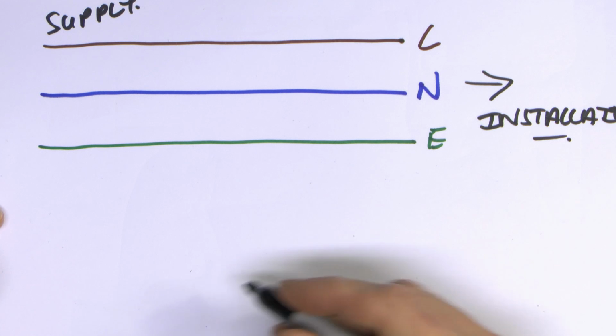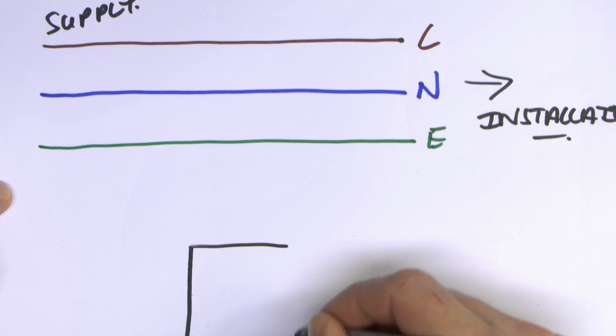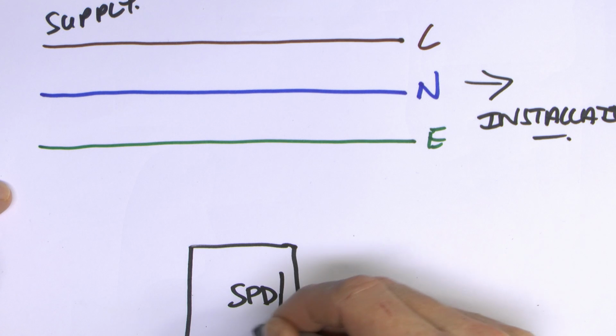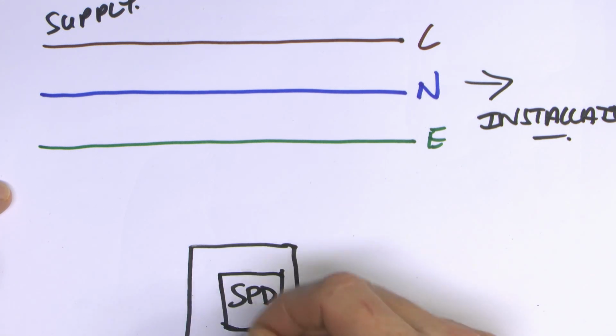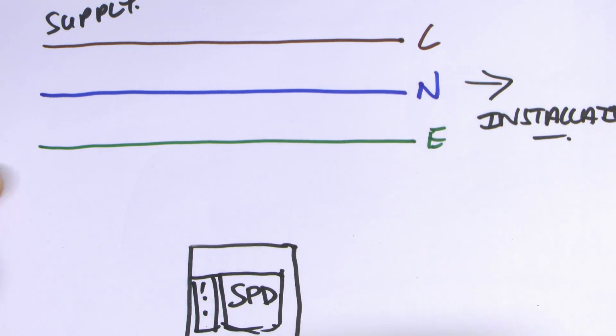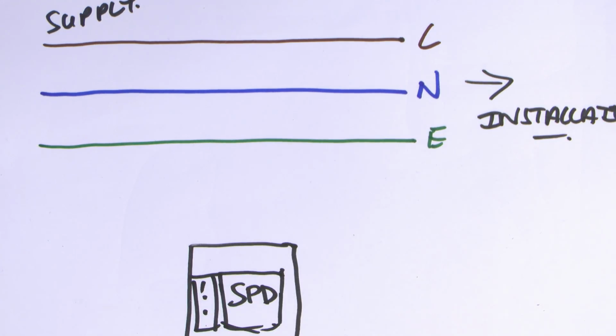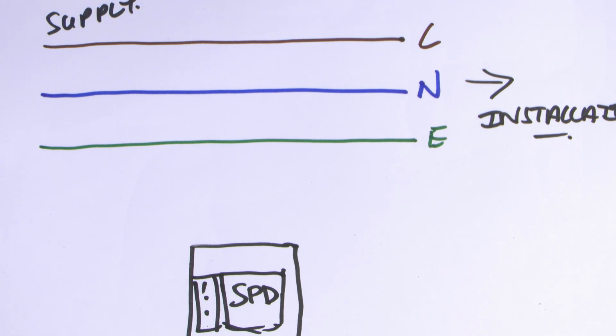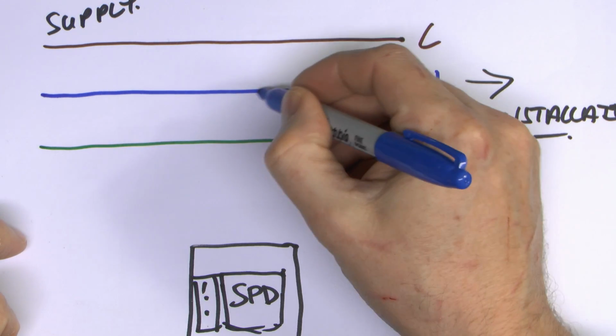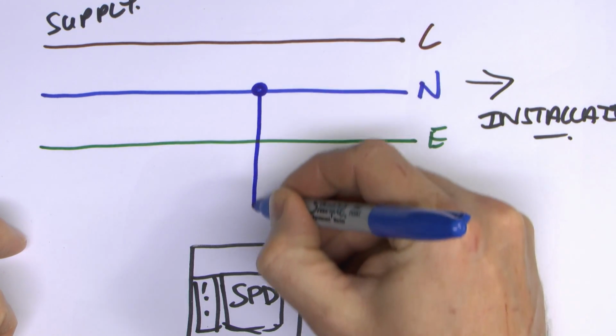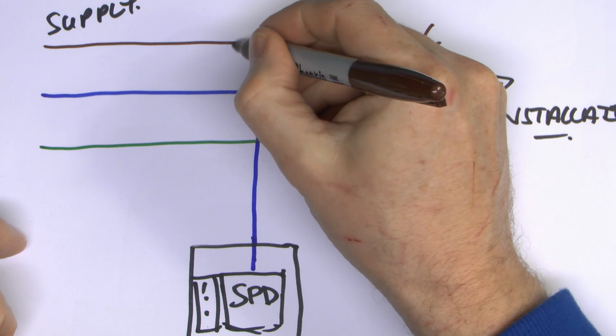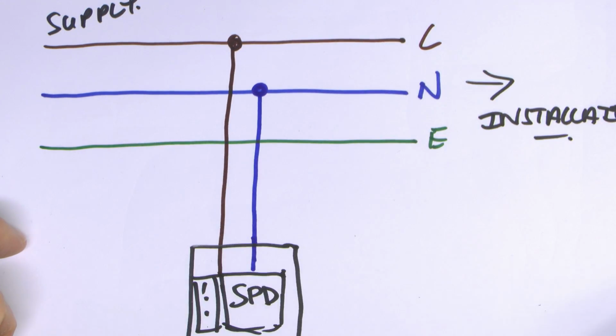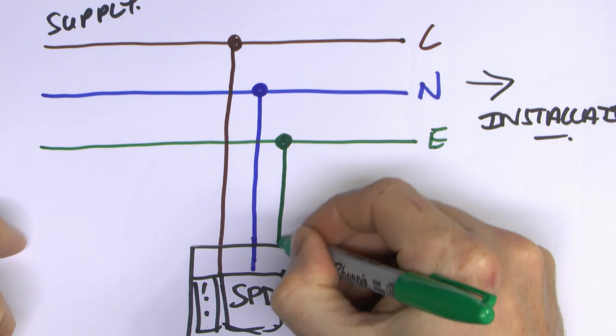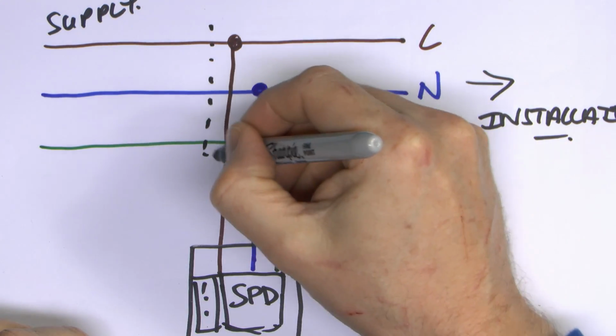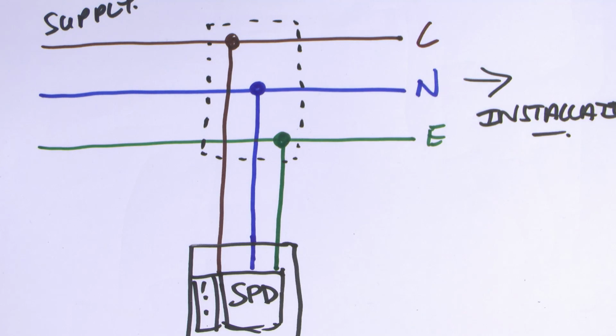Now one method of connecting a surge protective device is to locate it over here in a separate enclosure, and that would be inside there like that. Again, that may have a separate circuit breaker in there with it as well, or maybe not, depending on the type you've got. So, a separate enclosure, and they're fairly readily available. And then to connect it, you would take the wires from here with some kind of connection box and bring those across to the surge protective device over there. So they will just come over like that, and of course the earth would come over as well. And then this here could be, say, a set of terminals or a connection block or something like that, just tapped off of the incoming wires there.